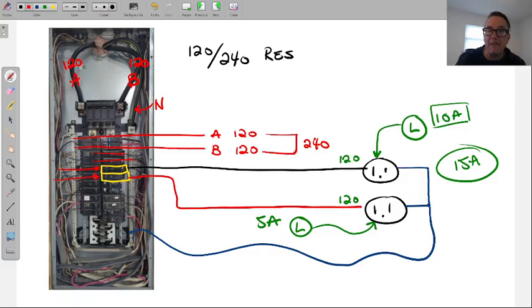Measured anywhere along the circuit, because we are AC. Either I'm measuring the neutral at the panel with my amp meter, or I'm measuring it over here at this outlet with my amp meter, or at the other one. It does not matter. AC is that way. Is that because it's a 15 amp receptacle? No. We'll get to why this number is. By the way, does anybody know why it's 5? More voltage, less amps? No, not Ohm's law.